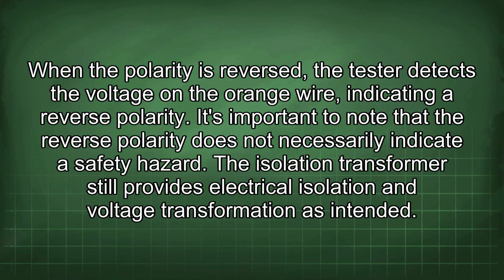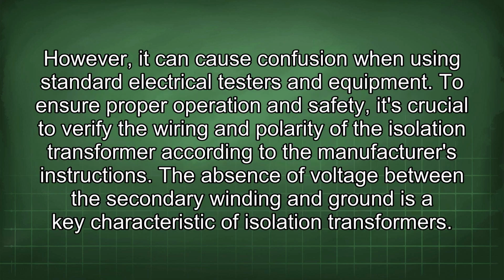It's important to note that the reverse polarity does not necessarily indicate a safety hazard. The isolation transformer still provides electrical isolation and voltage transformation as intended. However, it can cause confusion when using standard electrical testers and equipment. To ensure proper operation and safety, it's crucial to verify the wiring and polarity of the isolation transformer according to the manufacturer's instructions. The absence of voltage between the secondary winding and ground is a key characteristic of isolation transformers.